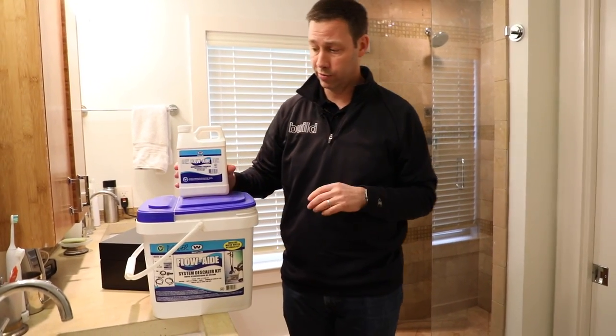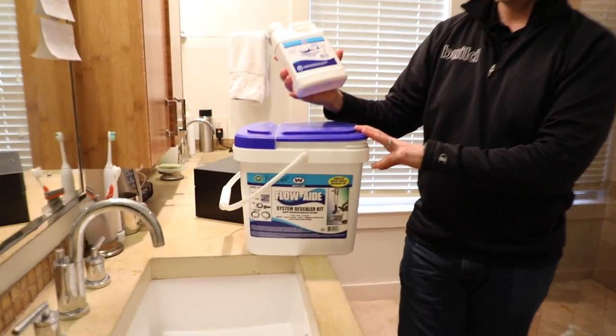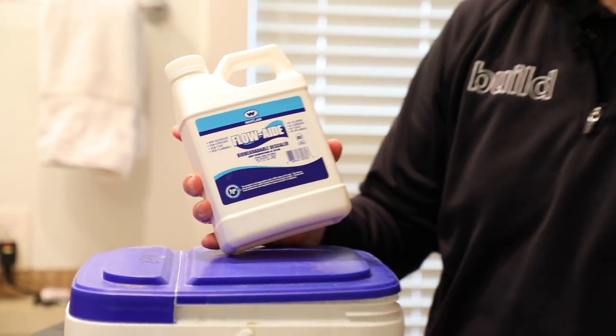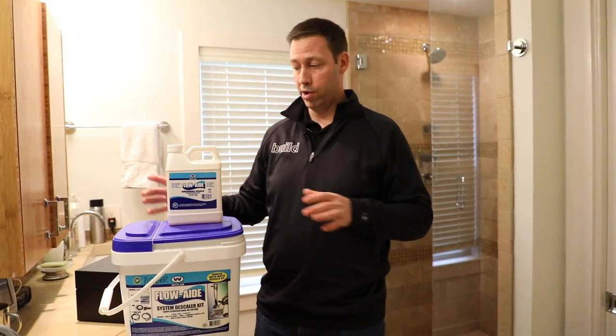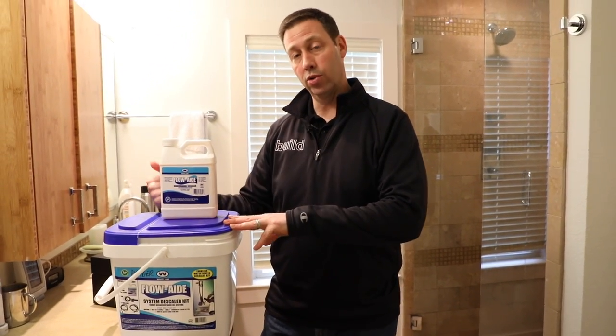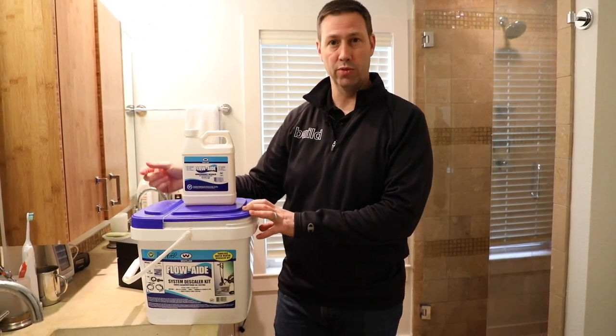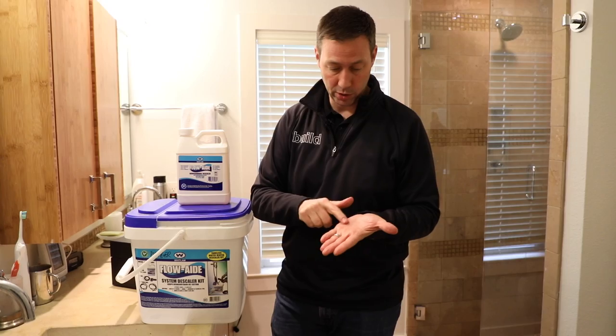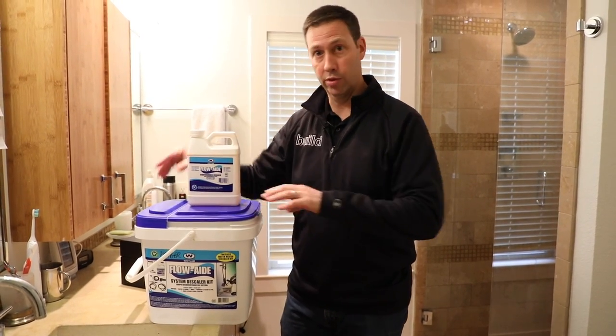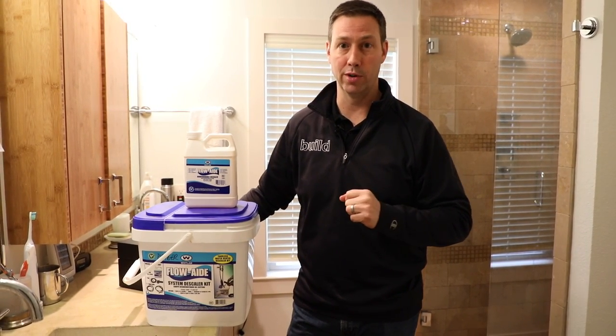I've made a bunch of videos — look in the description for a link. You can buy an all-in-one parts kit and you can buy this Flow-Aide, or you could do it with just plain old vinegar, but I prefer the Flow-Aide — it's a better descaler than just plain vinegar. Simple process: we're going to hook this pump up to the tankless unit, turn the water off, and run this solution through the copper boiler in a loop for about 30 to 45 minutes. This is going to take all those mineral deposits out of the boiler and leave them in the bottom of this bucket so we can throw them away. Then step two, we're going to come back right after we finish this.